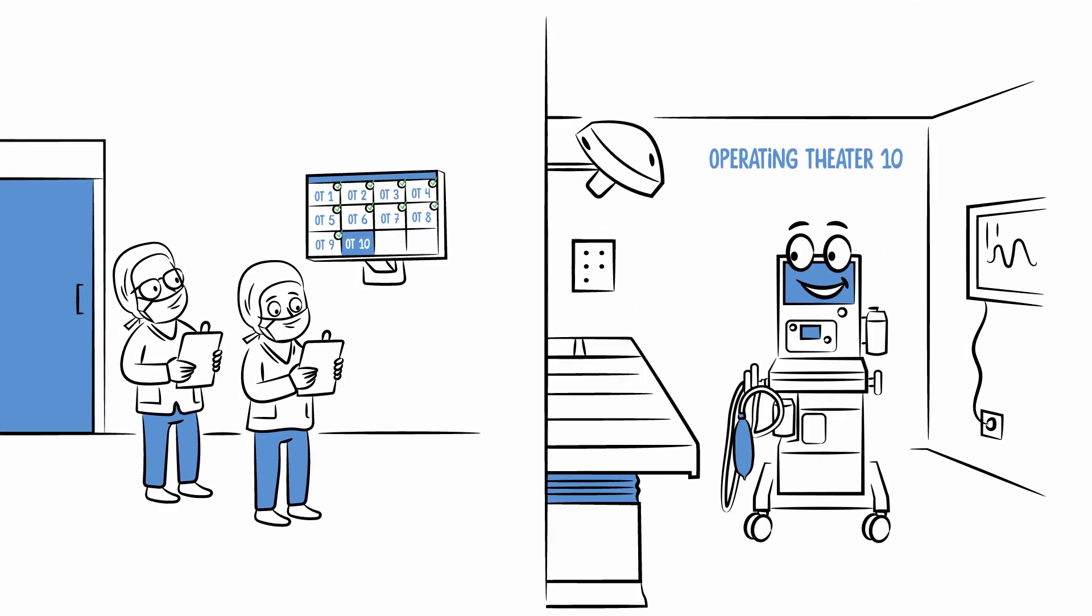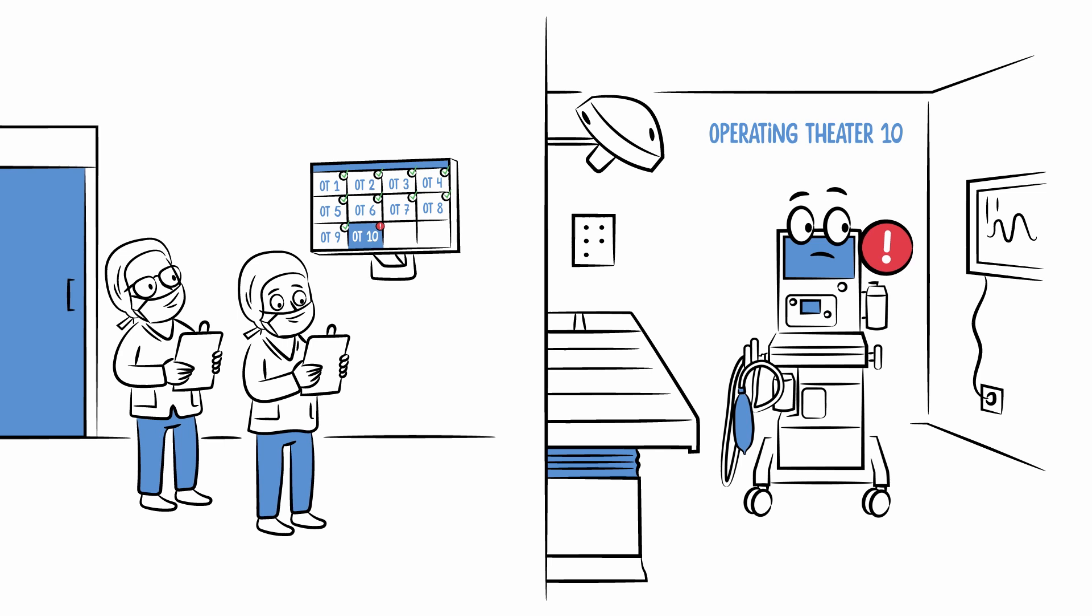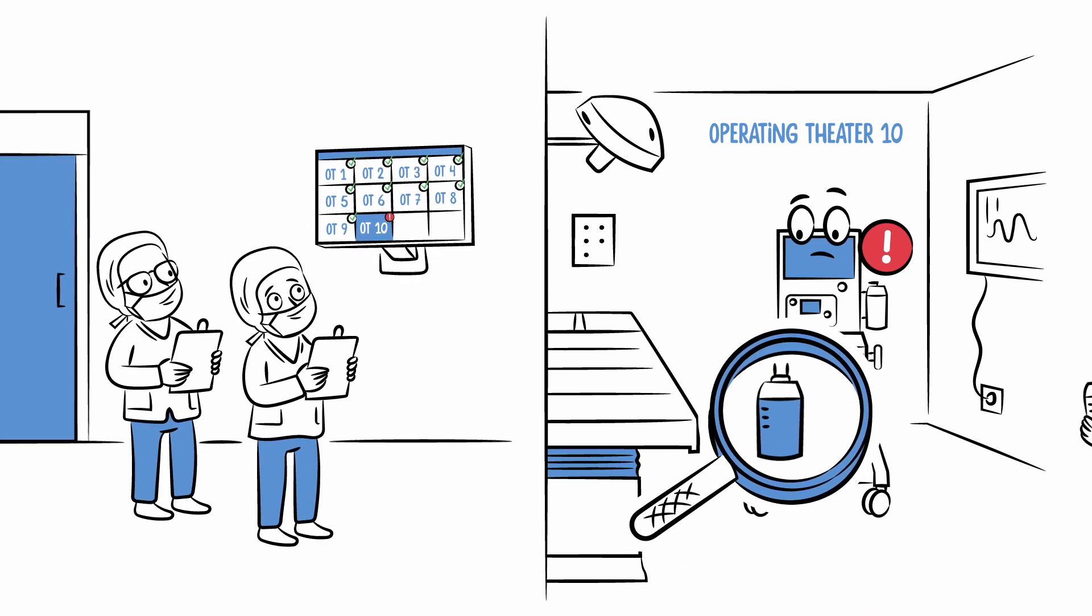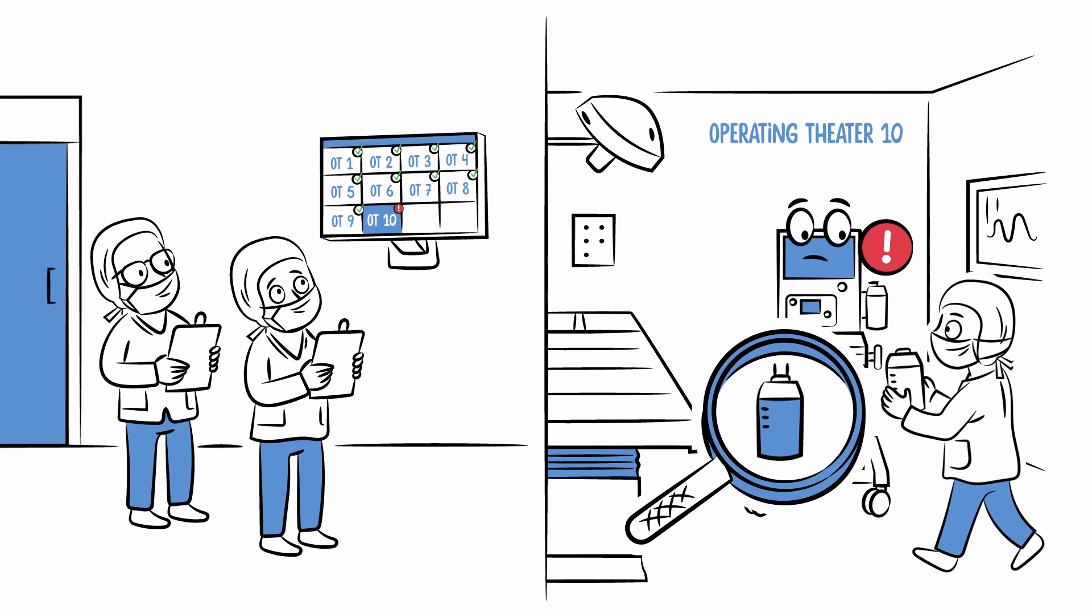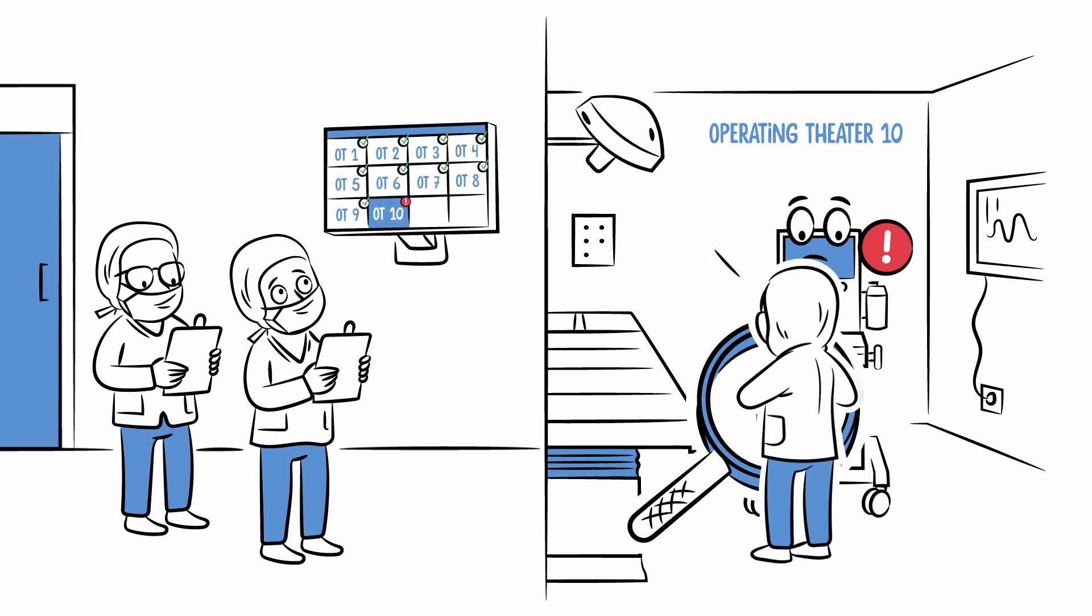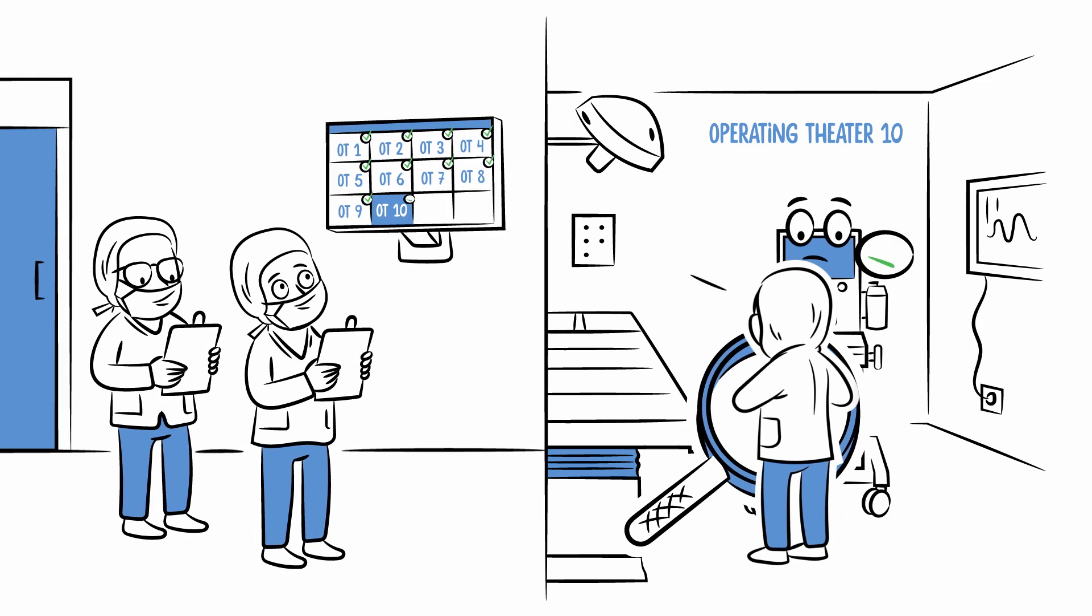In case an anaesthesia machine system test isn't completed successfully, the Self-Test Tracker acts as an assistance system and immediately provides staff with error information and troubleshooting steps.